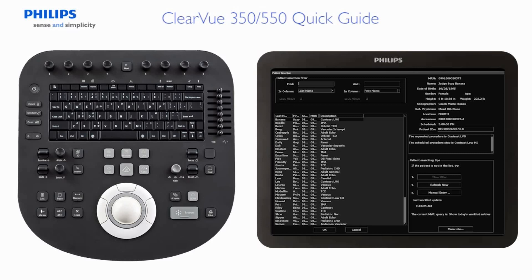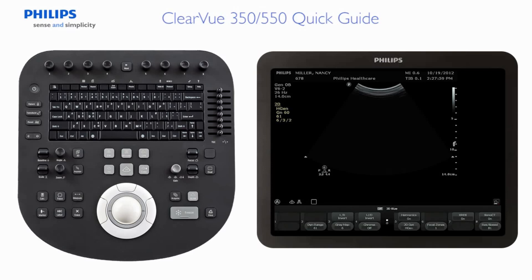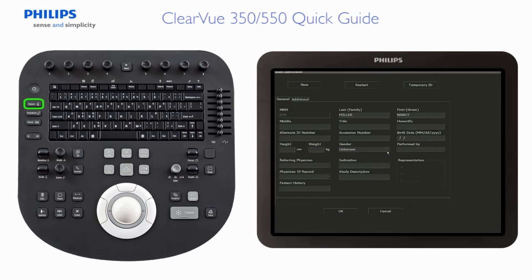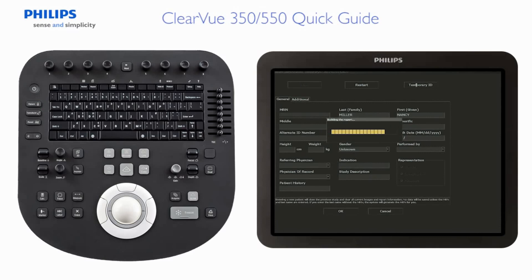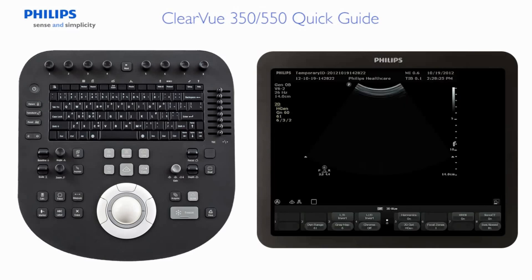Option 3: Temporary ID. If you need to proceed with the examination but you do not have the patient data information, use the Temporary ID option to begin a new exam. To select a temporary ID, press the Patient key and then click Temporary ID to begin imaging. Note: you may enter updated patient data within 24 hours to replace the temporary ID if the study has not been exported.